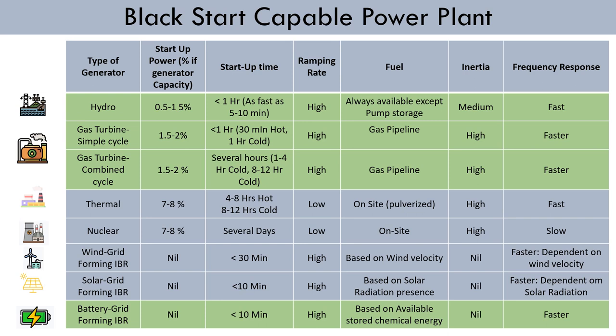The size and capacity of gas power plants are variable, ranging from smaller units to large combined cycle plants. This versatility in size enables them to meet the power demand requirements during grid restoration effectively. Moreover, gas power plants equipped with synchronous generators contribute to frequency stability and inertia, aiding in stabilizing the grid throughout the restoration process. In summary, gas power plants' quick startup time, high ramp rate, fuel flexibility, size adaptability, and ability to provide frequency stability and inertia make them a valuable resource for black start ability.